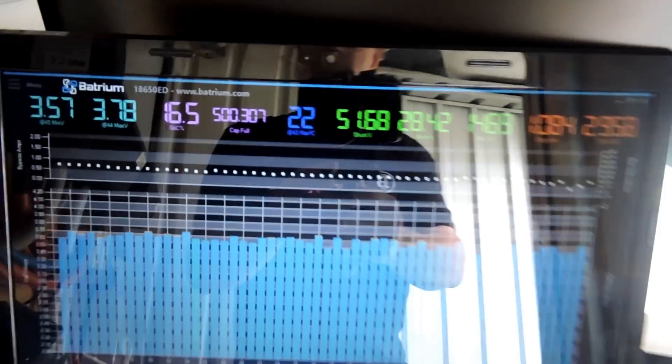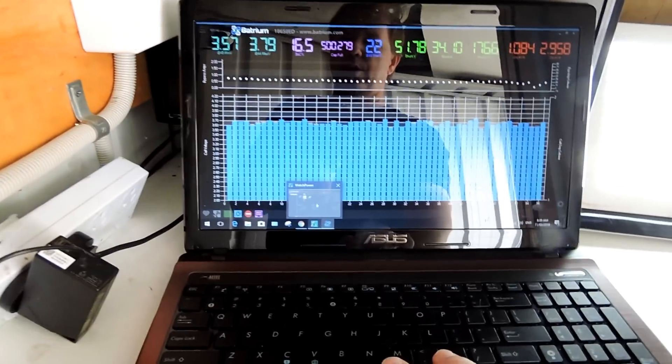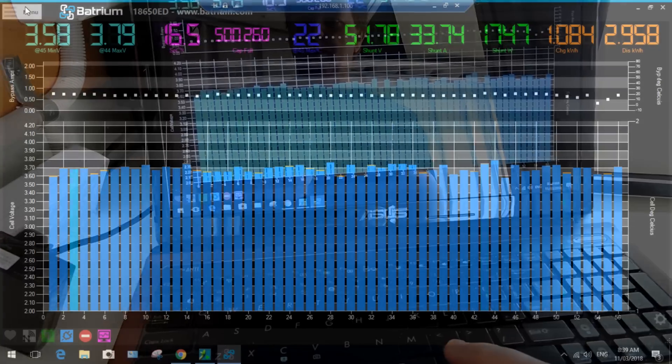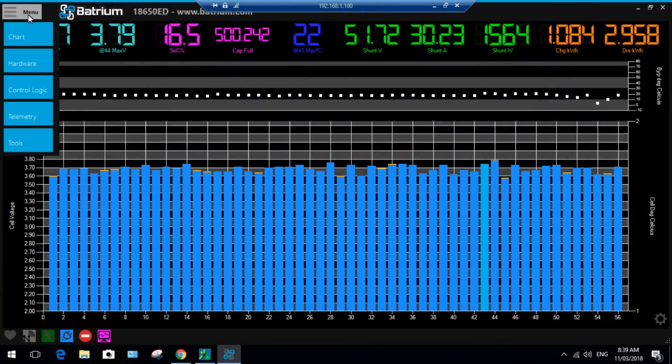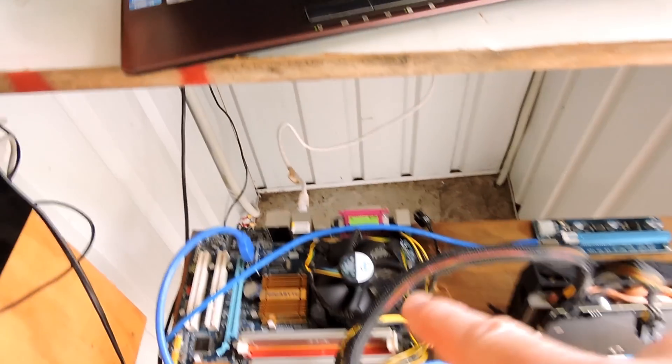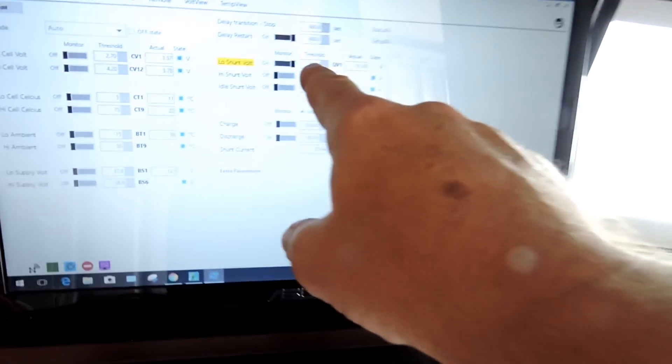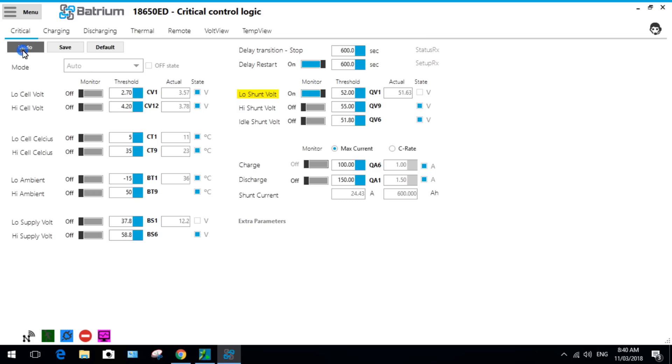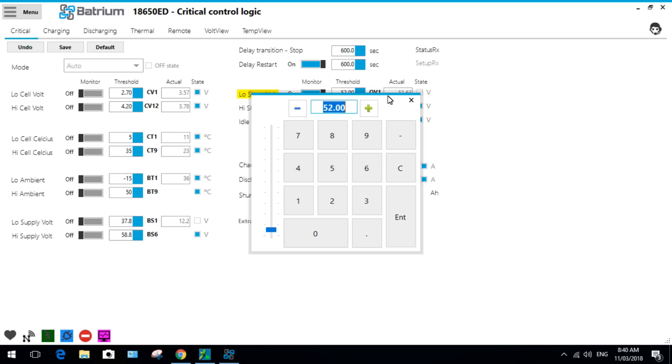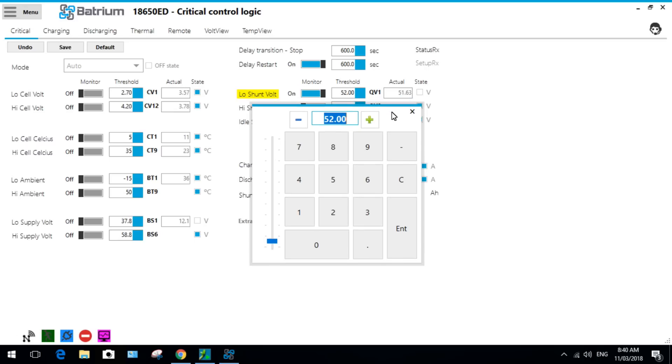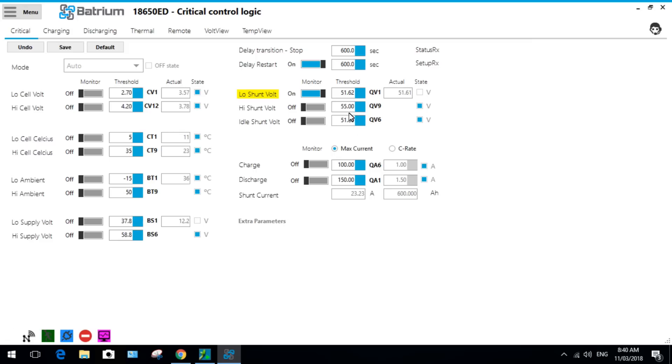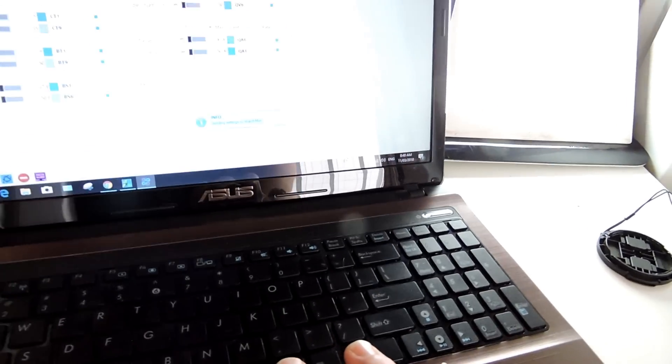So let's go over here. All we've got to do is click on menu, click on control logic, and we've got Low Shunt Volt. If I want to turn this back on or off, I've got to pass that threshold of 52 volts. Let's change that by clicking edit. It is on at the moment. We change this voltage - we've got 51.63, so if we go 51.61, so we go 51.62 and enter, then save.